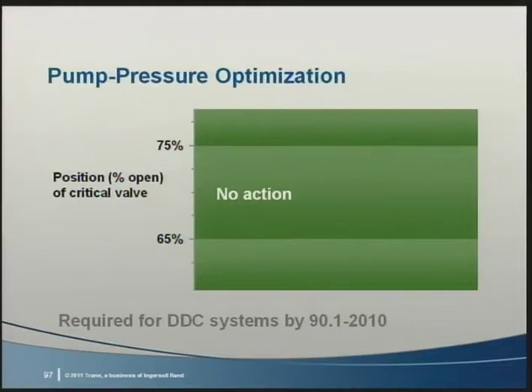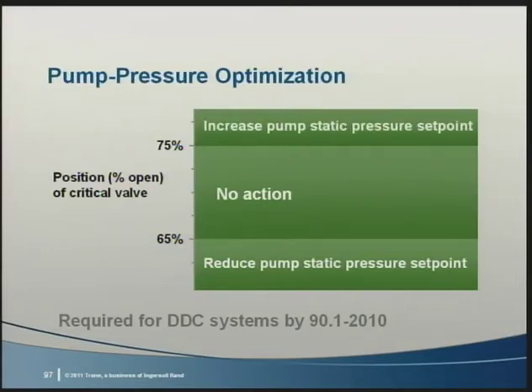If the worst case valve is between 65 and 75% open, we're already operating efficiently. If the system controller senses that all valves in the system are less than 65% open, it lowers the pump speed set point to reduce the water pressure. The valves will respond by opening to maintain the same water flow. If any valve is 75% open or more, the pump pressure set point is too low, and the control system will adjust the speed to increase the static pressure. In addition to the obvious pump energy savings, this method assures that zones aren't starved for water. This control is required by ASHRAE 90.1-2010 in many systems with direct digital control valves.